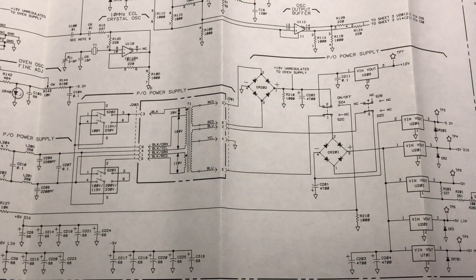Now I have the frequency counter plugged into an isolation transformer and a very light fuse protecting the isolation transformer and of course this instrument. So if there is a problem, that fuse will just go away and it'll protect things and keep things very safe that way. And the isolation transformer is good practice when you're working on an instrument with the cover removed and you're working around that AC line. So again, good practice to use an isolation transformer.